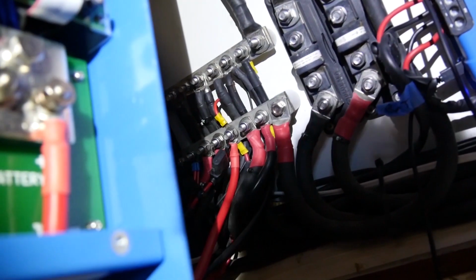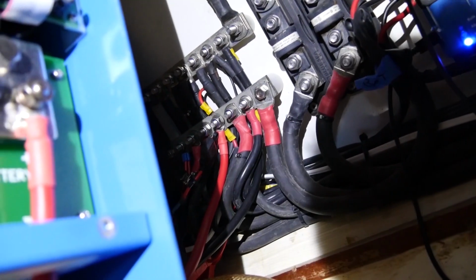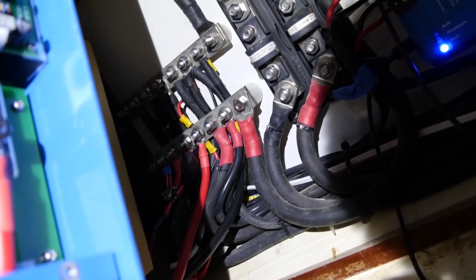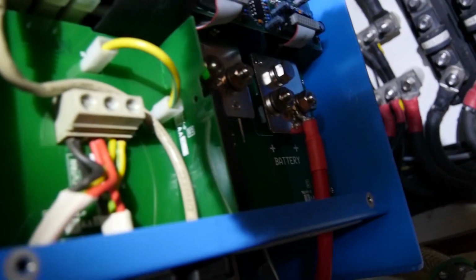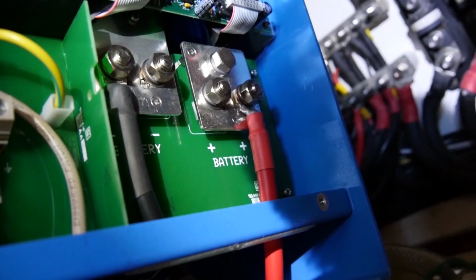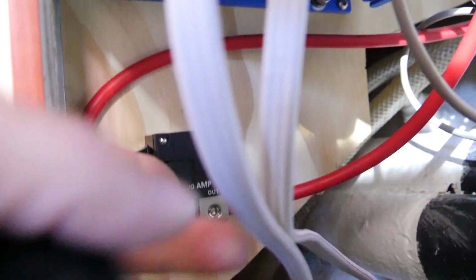I've now cabled both the negative and positive DC terminals from the bus bars to the inverter - you can see them both connected. The positive comes through a circuit breaker I've installed, which is currently off, so I'll test it by turning the breaker on.